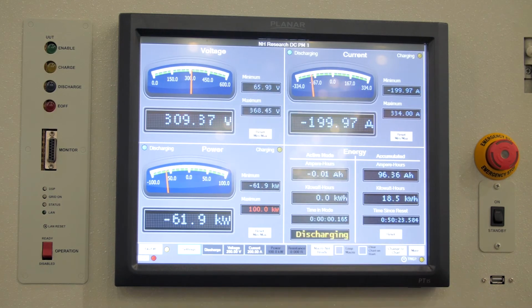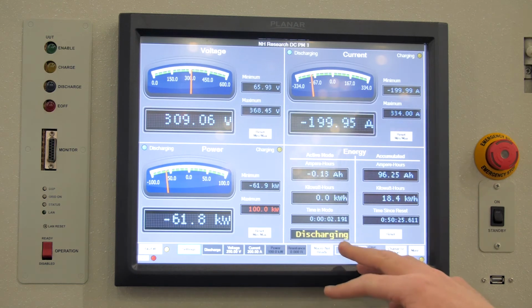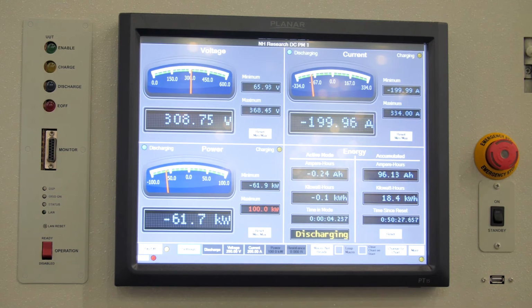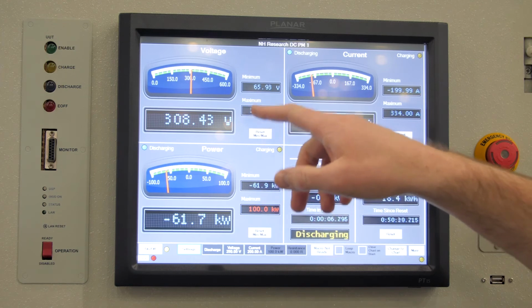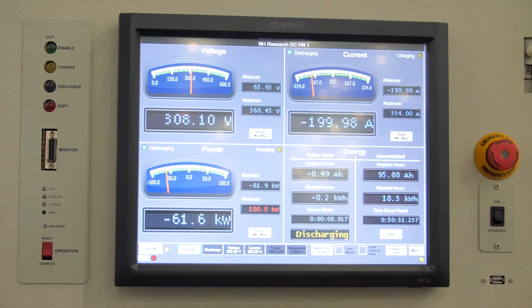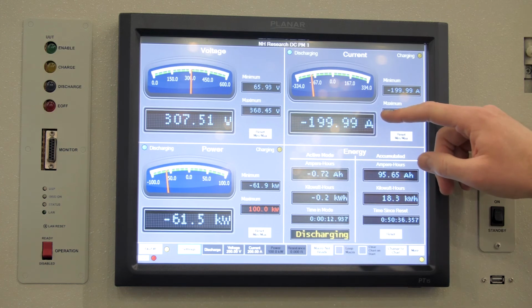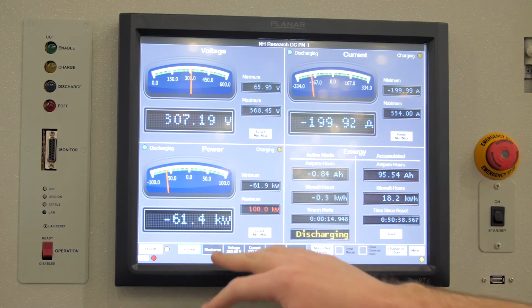When we hit OK, you'll see our mode has now changed. We're now in a discharge mode. You'll see this voltage start to come down. This would be your battery voltage. In this case, for a battery test, starting to drain. We're measuring that 200 amps. And then you can see where your power is as well.